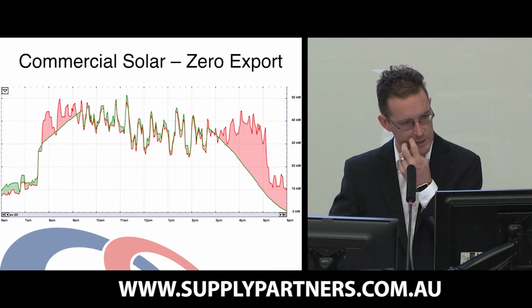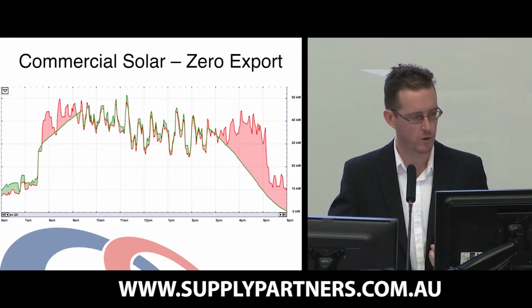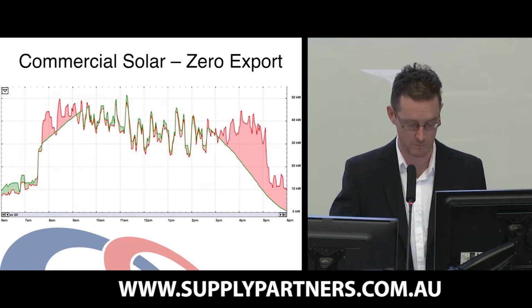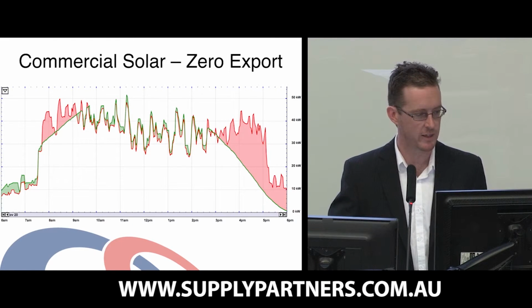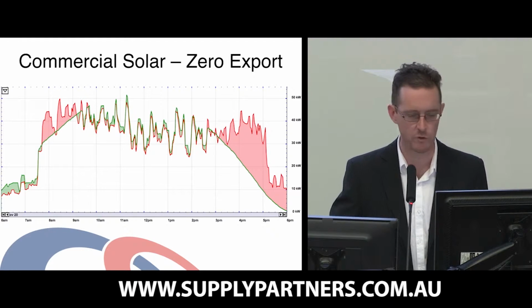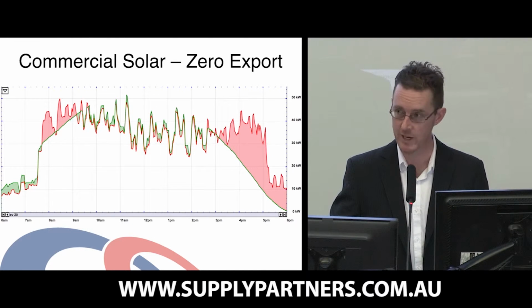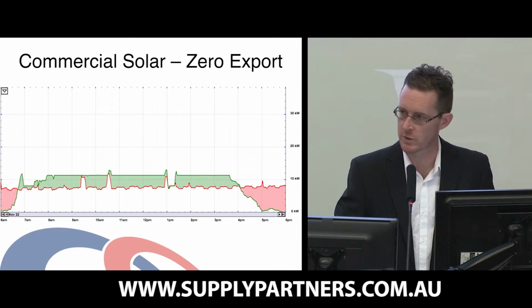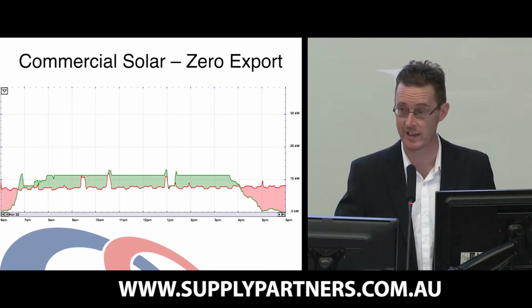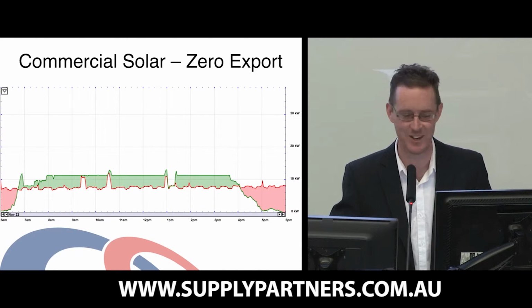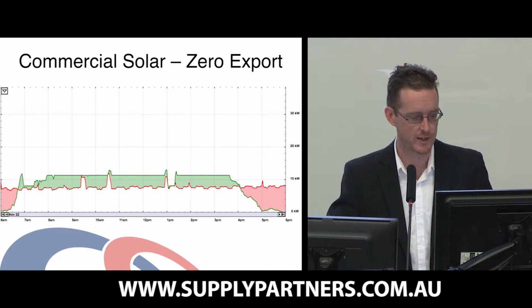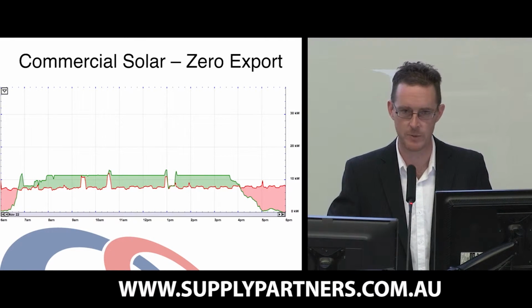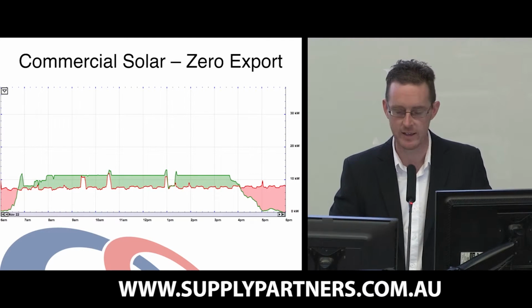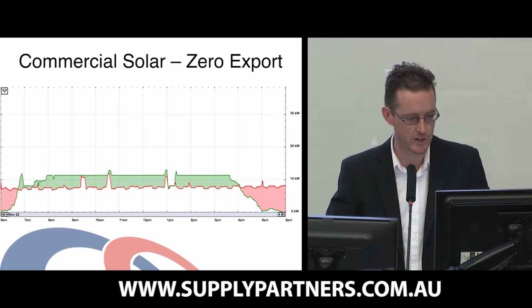So here's an example of a zero export system, a 60 kilowatt installation on the Gold Coast. You can see that this was actually a beautiful sunny day. If there had not been an export limitation system on this install, you would have seen a classic green bell curve for the solar. But because the load was up and down, the solar system was ramped up and down to follow the load. On a weekend, because this building on the Gold Coast is an office building and there's no one there on the weekend, you can see that we have actually been allowed to export a little bit because that particular site has a dedicated transformer. So we're allowed to export a bit there.